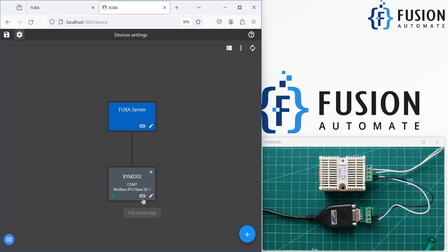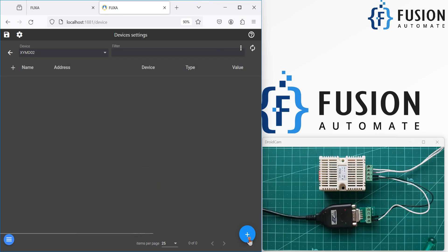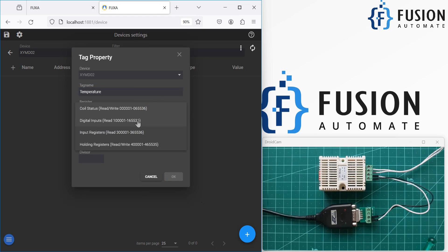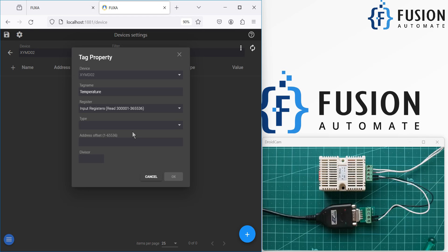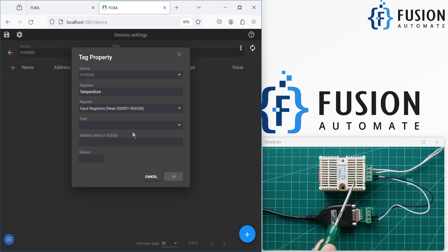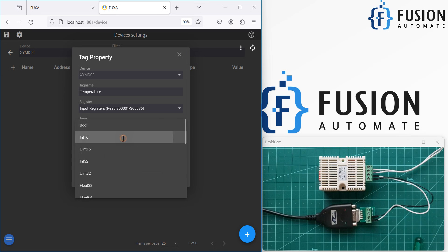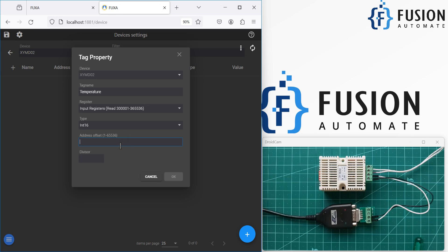We will click on the 'Edit Device Tag' button, then click the plus icon and provide the tag name as 'temperature'. The register we are going to read is the Input Register, because this device provides data on the Input Register. Input Register 2 is for temperature and Input Register 3 is for humidity. We will provide those details here and the type is Integer 16.